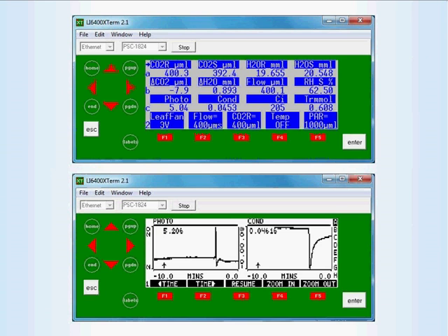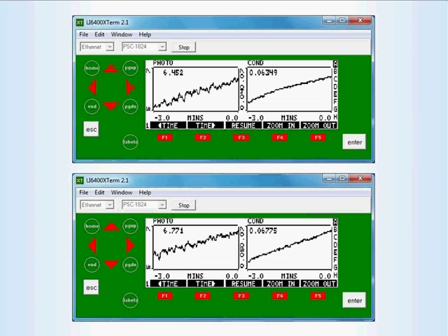With the higher chamber humidity and the reduced mixing fan speed, you can see that the leaf has begun to recover again, from these two strip charts, which were taken one after the other. Stomates tend to close down faster than they will reopen. So watch out for the response of leaves to being clamped into the chamber, and be ready to take quick action, because they will close up and they'll take a long time to reopen.